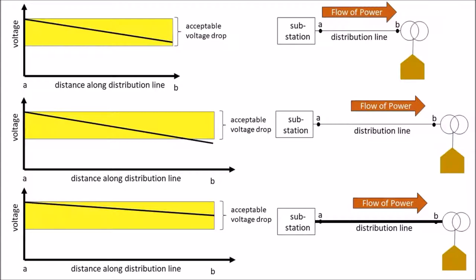Our way around this would be to install larger conductors, shown in the bottom figure, so the distribution line is more substantial and the voltage drop stays within range. So the further away a community is, not only does the line need to be longer to reach it, but the conductors need to be bigger so we don't have a voltage drop problem. It becomes more and more expensive the further away you go.